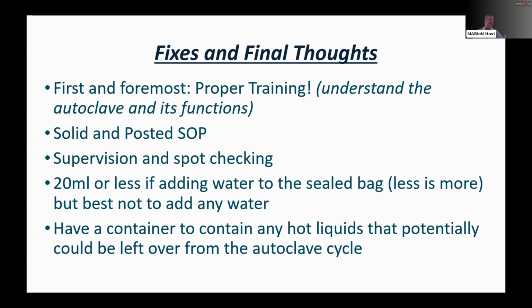Most of the time I see it, they do have EDS, and most autoclaves now have an effluent system that preheats the drain area, so that when it comes in contact, it's getting about 320 degrees heat. You have to remember, anything coming out of your steam generator is at 80 to 100 PSI, running at about 380 degrees. Even though your autoclave runs direct steam, most of them have that now. That was one of the things that was addressed. If you have an older autoclave, probably not, but newer ones do have effluent systems that can treat that.